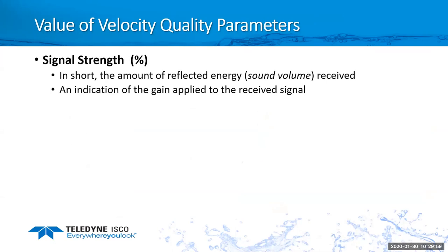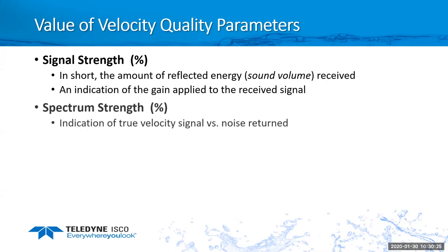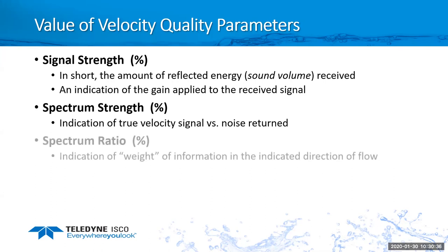Other ways to measure reverse flow or determine the quality of your area velocity sensors, like with the 2150 and the 350 AV sensors, we have diagnostics built in for signal strength, which measures the amount of reflected energy received. It's an indication of the gain applied to the signal. A lot of times you're going to see this around the 60% range. The spectrum strength is the return signal from the signal that's been sent out. It's an indication of the true velocity versus the noise.